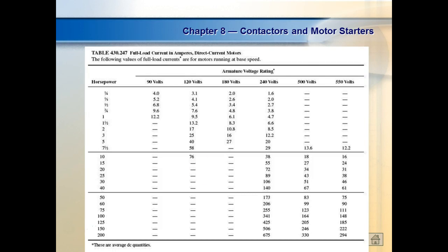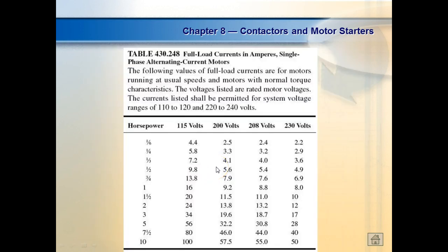Table 430.247. This is single phase motors. This is table 430.248 out of the National Electrical Code. But you're not going to find hardly any single phase motors over 10 horsepower, so that's the highest they have. But if I had a 10 horsepower motor and I was running it on 115 volts, it would pull 100 amps, right? But now y'all know y'all don't have any 10 horsepower motors in your house. Most of y'all are down in this range down here. Quarter horsepower. You might run into a half horsepower motor, probably running your compressor if you have a big air compressor.